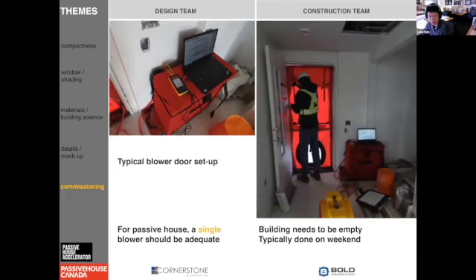So blower door test for air tightness will be one of the key elements at the commissioning stage. One of the things we're going to do is go to the 6th floor to do a mock-up for the whole building to find the leaky points on that one unit. Yeah, so what we've done is we've isolated one suite. We're going to be taping the floor, doing special preparation around it so that we have one good sample to test our exterior wall, our parapet, and our roof assemblies to see how we're doing.